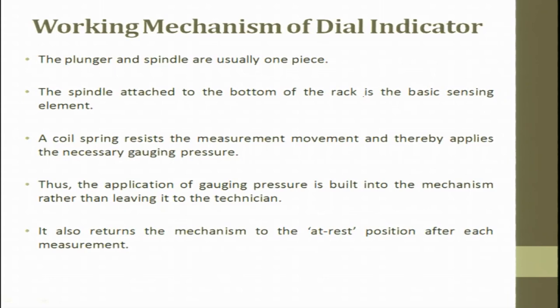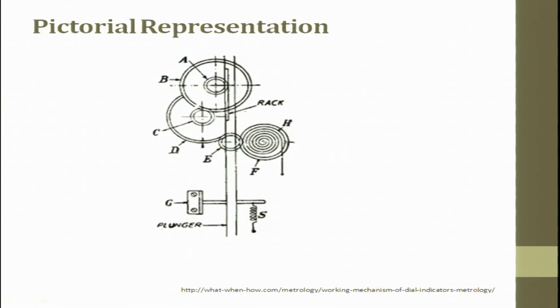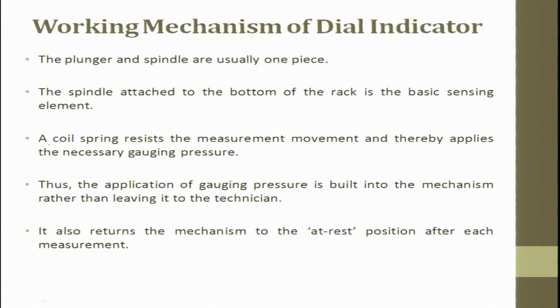The plunger and the spindle are one piece. The spindle attached to the bottom of the rack is the basic sensing element. Here is a rack and a pinion — when you push the plunger, the rack moves, then the pinion moves; if you have a pointer on the pinion it also moves. A coiled spring resists the measurement movement and thereby applies the necessary gauging pressure. When the plunger goes up, there must be resistance, so we use a coil spring. The application of the gauging pressure is built into the mechanism rather than leaving it to the technician.